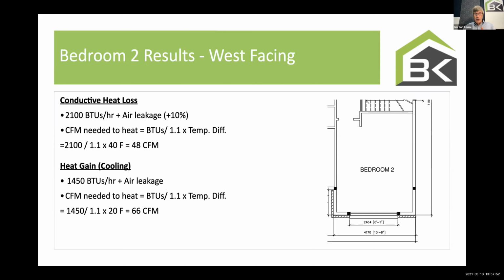And so this is where homeowners get concerned. One child's bedroom is fine. The other's bedroom is always cold in the winter and hot in the summer. It's the same size room. This can't be. So what? And I just did one of these last week. And for heaven's sakes, let's measure the airflow. On the design, let's measure the airflow. I don't have to wait for the design day, right?